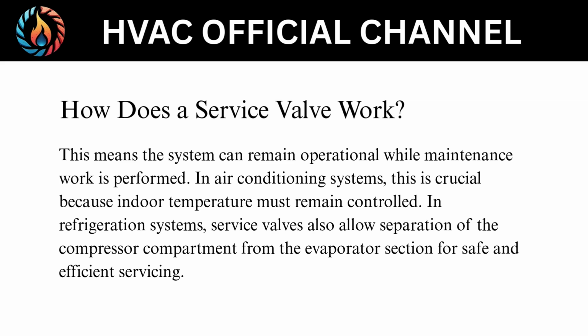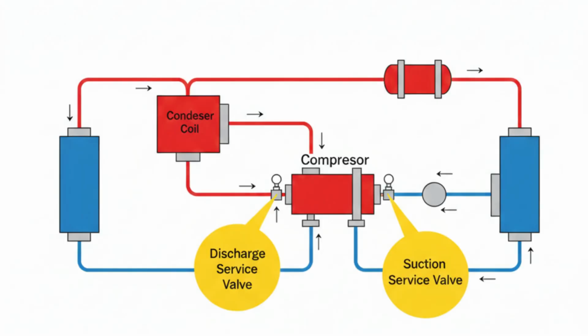In air conditioning systems, this is crucial because indoor temperature must remain controlled. In refrigeration systems, service valves also allow separation of the compressor compartment from the evaporator section for safe and efficient servicing.